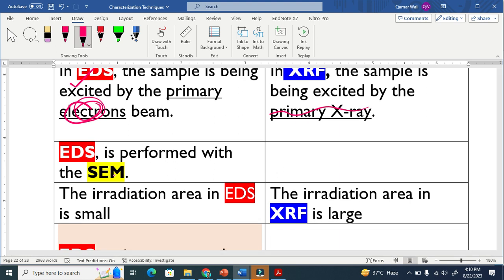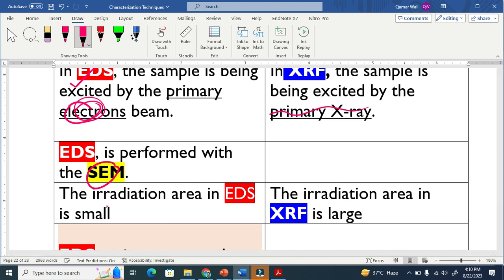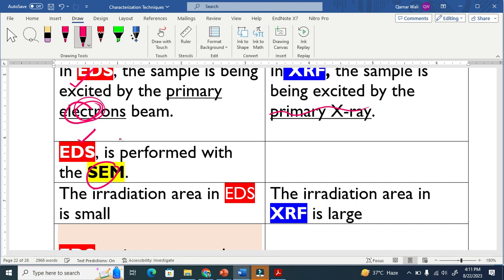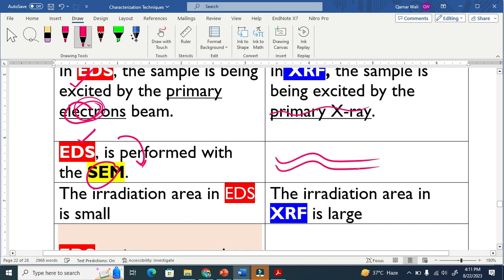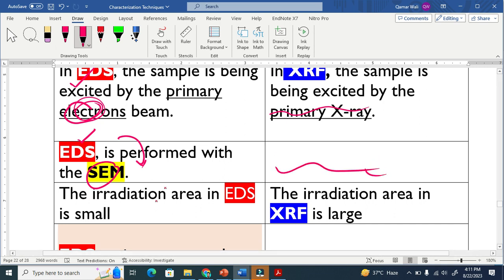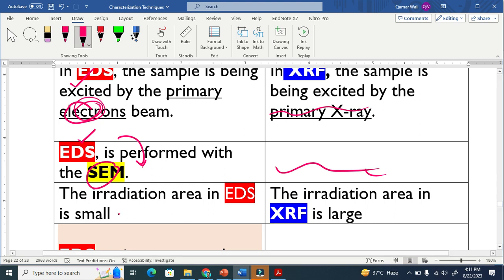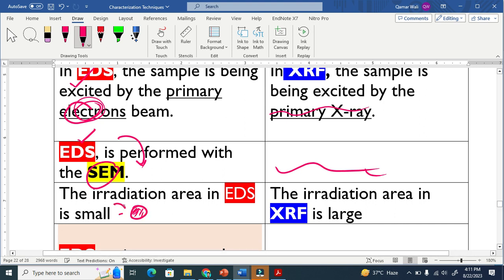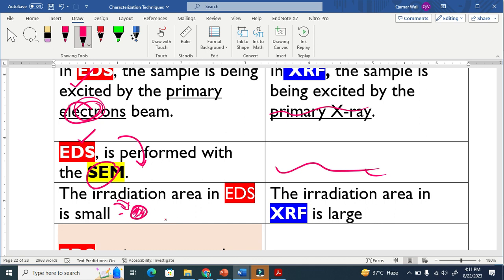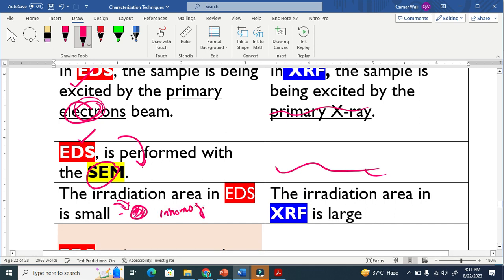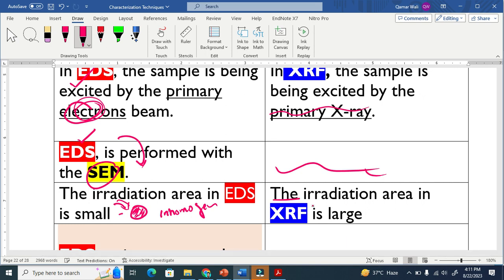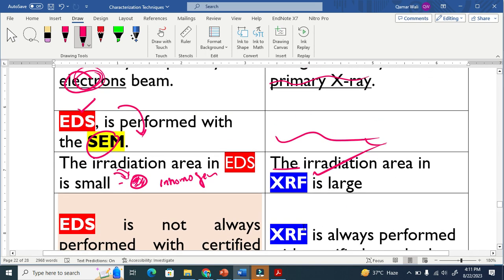EDX is always performed along with SEM, scanning electron microscopy, because this EDX is basically embedded in scanning electron microscope, but there is no such requirement for XRF. The irradiation area in EDX is small. This means that because we irradiate electrons, that area is small. So they may cause trouble if we have an inhomogeneous sample, but the irradiation area in XRF is large. There is no such issue that exists.